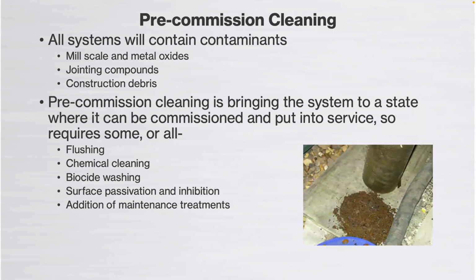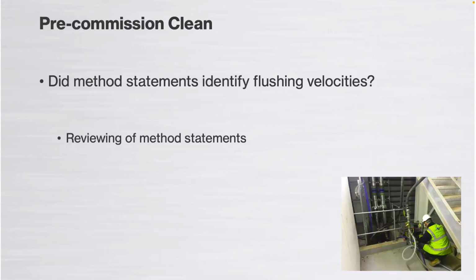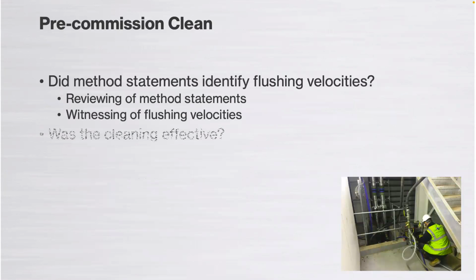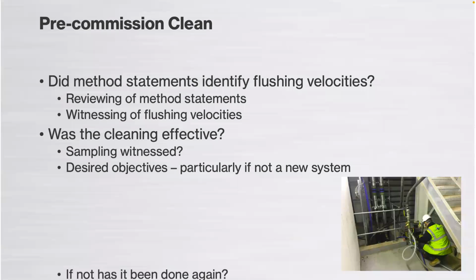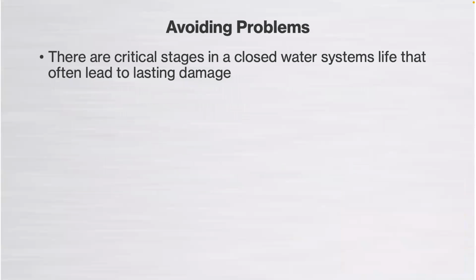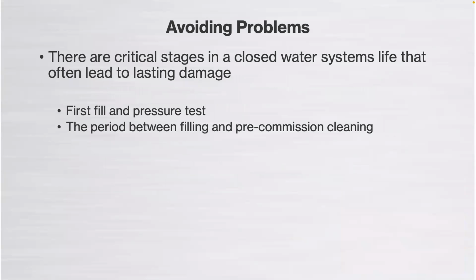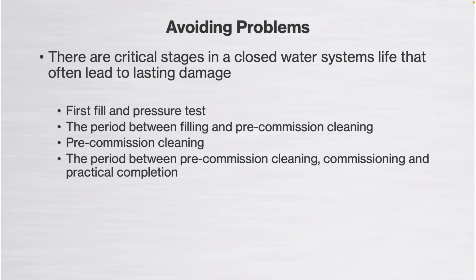Pre-commission cleaning, essentially. So for pre-commission cleaning and so forth, we need to make sure that in the methodology we're covering anything from flushing, velocities, any chemicals that we're going to be using, and certainly maintenance thereafter. In terms of pre-commission cleaning, velocities are key. So any witnessing and reviewing method statements and making sure any sampling was taken. If it hasn't been done properly, have we done it again? So just to avoid problems, fill and pressure test.